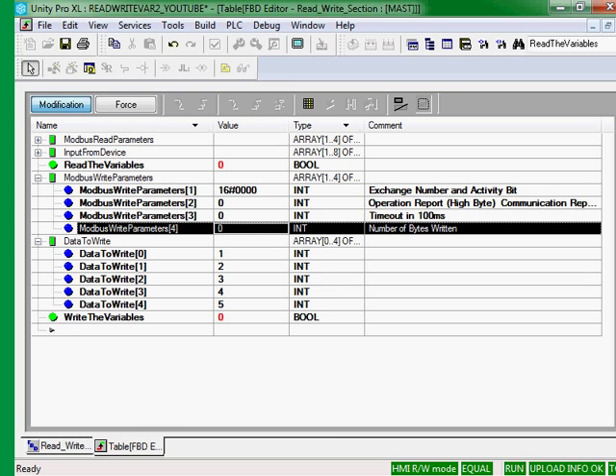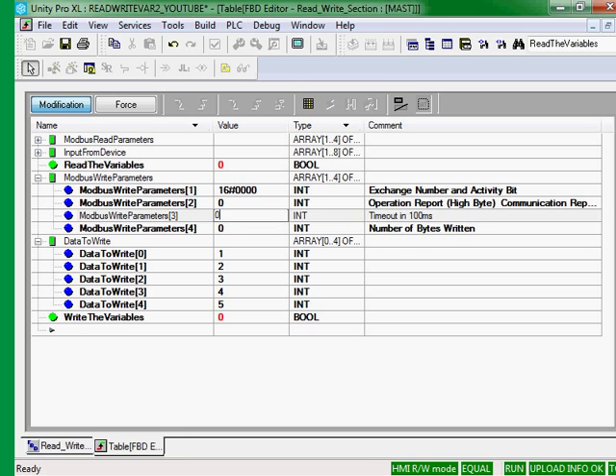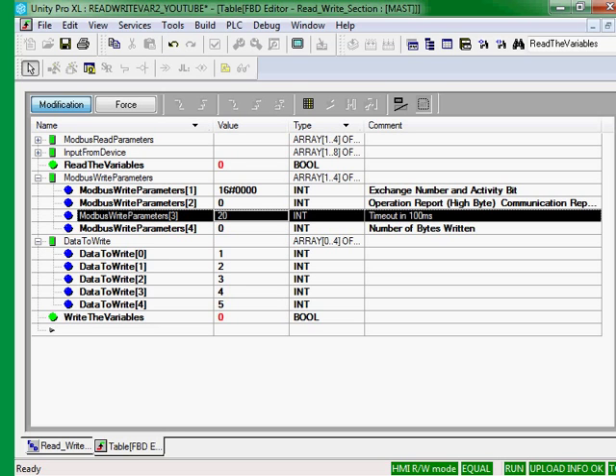These are the Modbus write parameters. Again, we know we need a timeout because that is very important. Because if the cable were unplugged, the timeout of zero is infinite. And we don't have that long to wait.